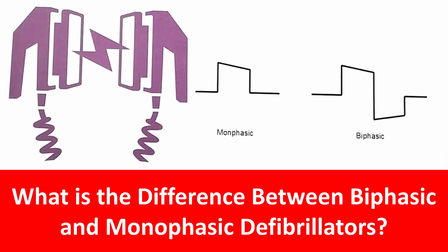After sensing the thoracic impedance, the device can adjust its internal resistance so that the set joules are delivered properly, because everything is computerized. Modern day defibrillators can then deliver the shock and also synchronize. In cardioversion, it is synchronized to the R wave, so that it does not induce fibrillation by itself. So there is a lot of technology involved in a defibrillator. Thank you.